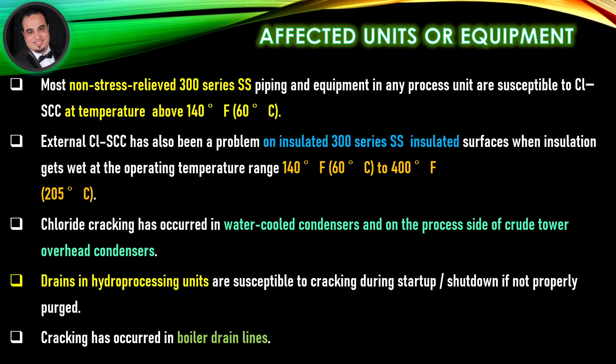Affected units or equipment: Most non-stress-relieved 300 series stainless steel piping and equipment in any process unit are susceptible to chloride stress corrosion cracking at temperatures above 140 degrees Fahrenheit. External chloride stress corrosion cracking has also been a problem on insulated 300 series stainless steel surfaces when insulation gets wet at operating temperatures ranging from 140°F to 400°F.